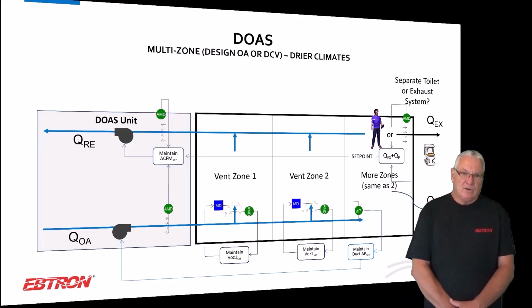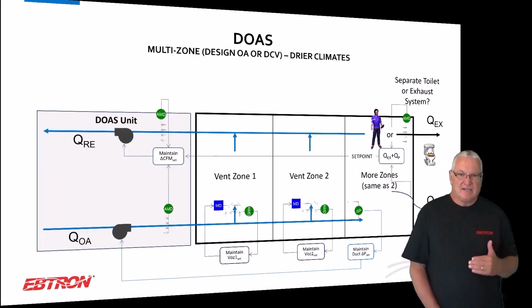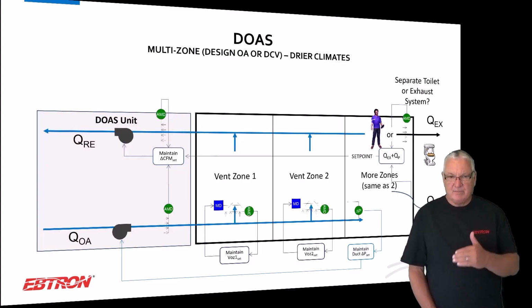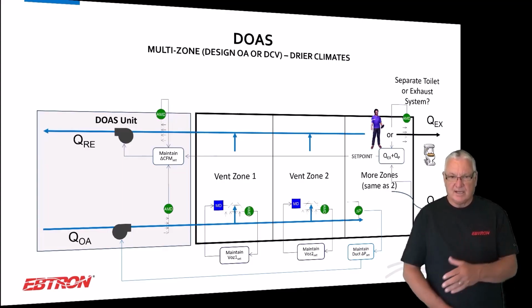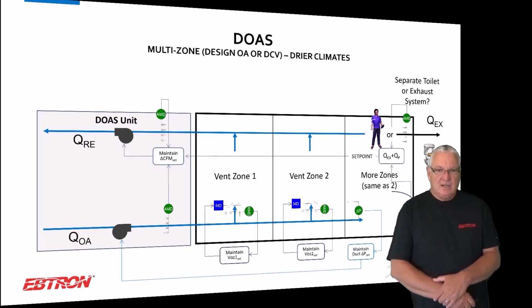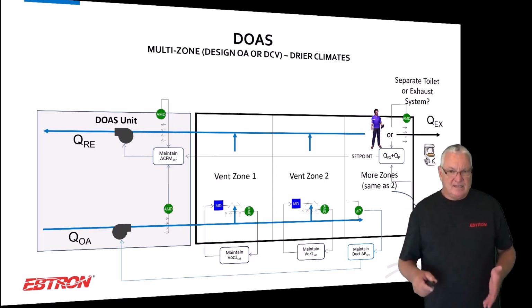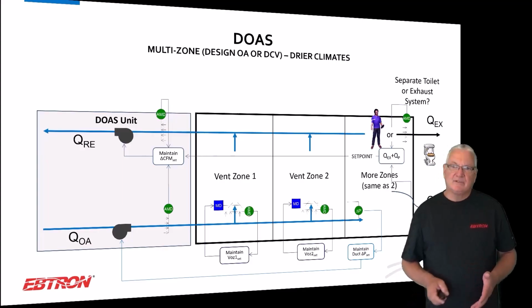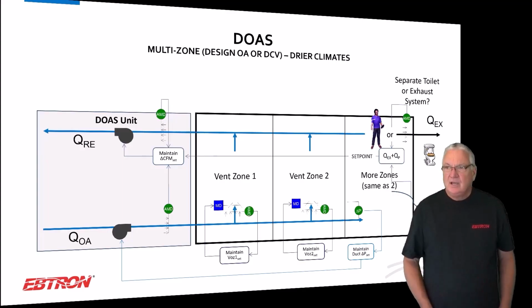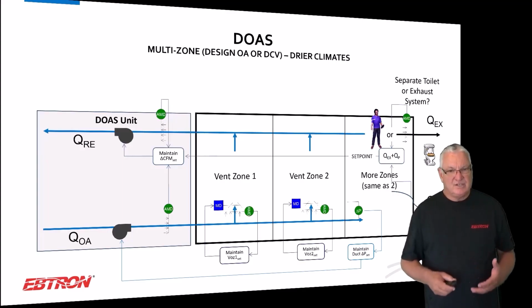It's like when you look at the outside air side of a DOAS system, that's multi-ventilation zone, and there's going to be some variable zones on DCV. It's almost like a VAV system from the supply side. I mean, you would never think about controlling your temperature zones on a VAV system without maintaining flow rates, okay, without measuring it. And so I strongly suggest you measure the flow.